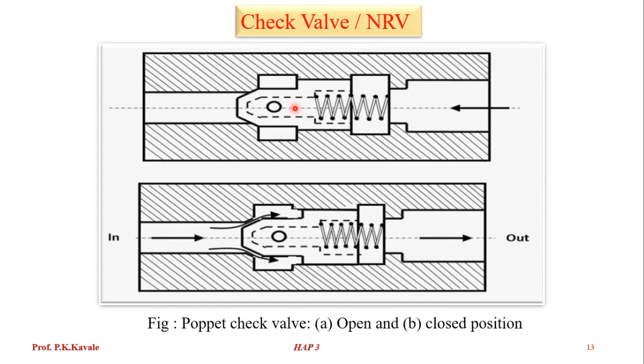In another type of check valve, the geometry of the restricting element has changed — instead of a spherical ball, it is a wedge shape. This is called a poppet-operated check valve. The difference is in the geometry and performance; the reliability of this poppet check valve is somewhat better compared to the spherical type, and leakages are less.